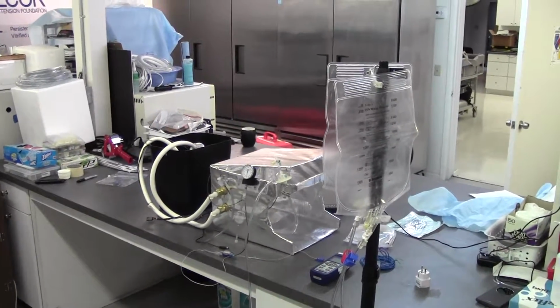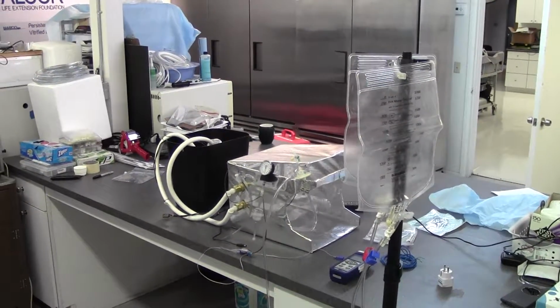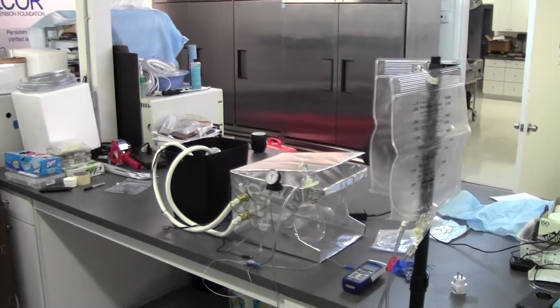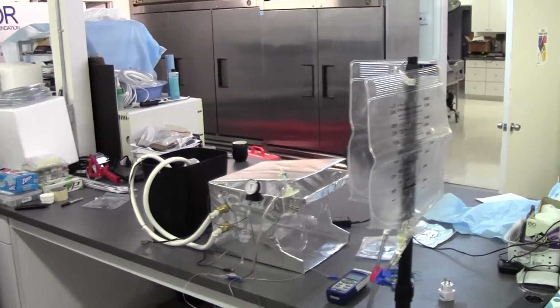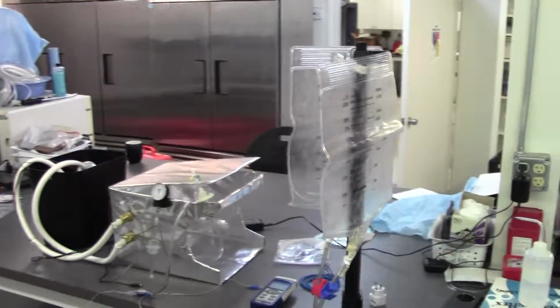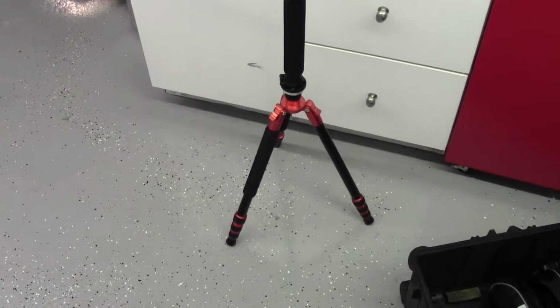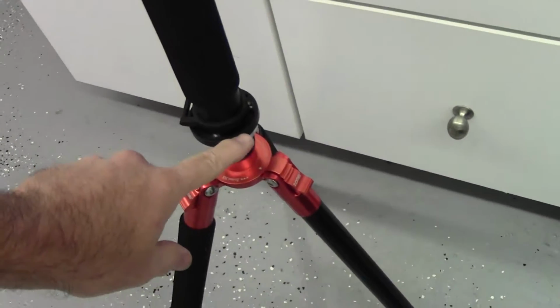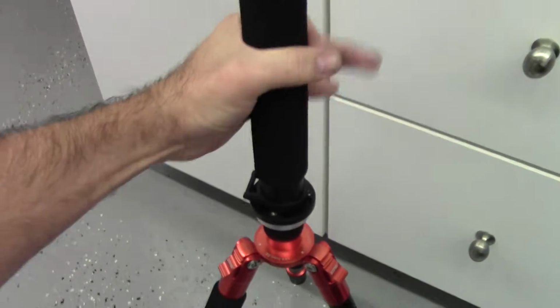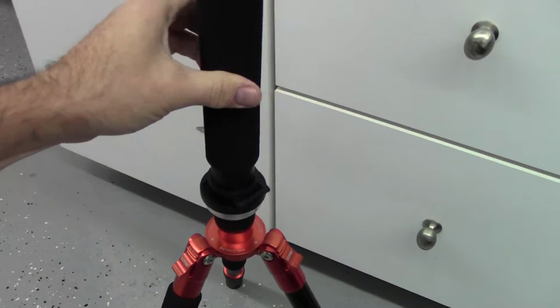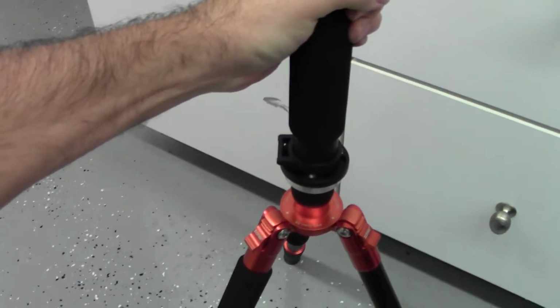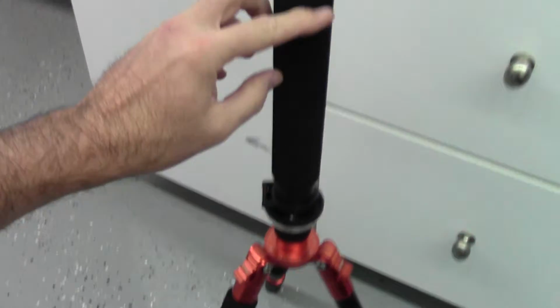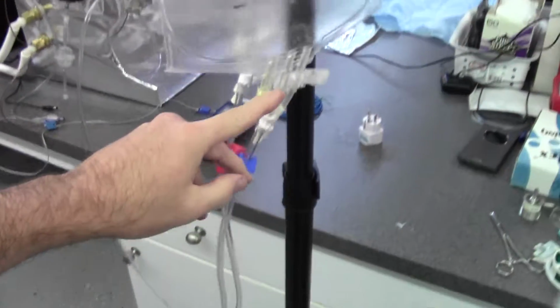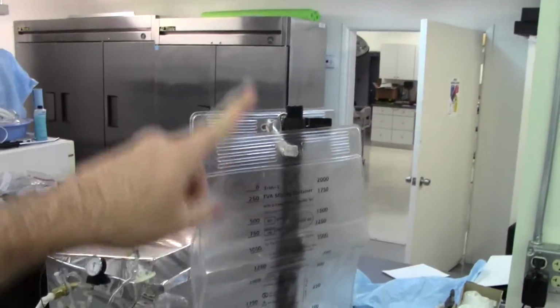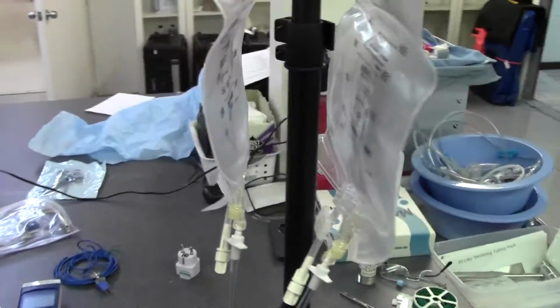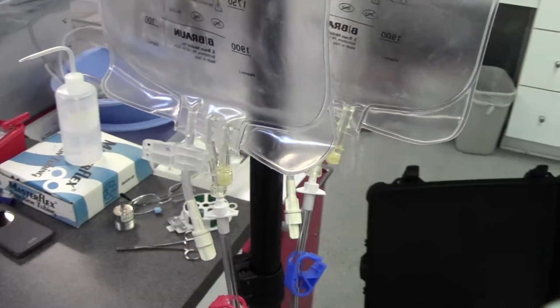Okay, this is our 5-minute overview of the gravity feed step ramp neuro field system. The first thing you'll notice is we have two bags, and they are hanging on a tripod stand. These are joined together here. You turn this to unscrew it, so that's how it comes out of the travel case, and you screw these two pieces together, and then you extend these upwards to give you the height that you need in order to have the gravity feed give the pressure that you need for the patient.